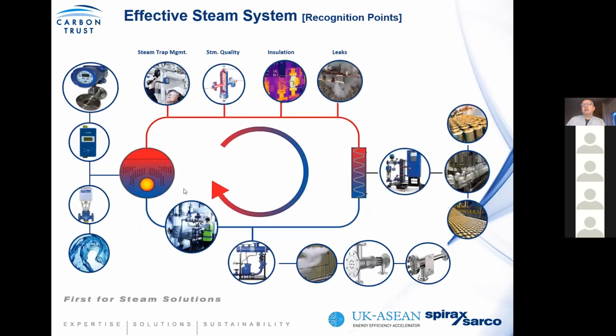So when we look at a steam system, we need to understand what contributes to an efficient system. We'll be talking about boiler efficiency and how we can achieve efficiencies, and as was introduced, there are certain parts of boiler operations which can achieve very attractive savings. We also need to look at the hot well system, or your boiler feed water system, and most importantly, its functionality, including the quality of feed water, the type of feed water, and what it means for the efficiency of the boiler. It's also important that we look at the steam distribution system.